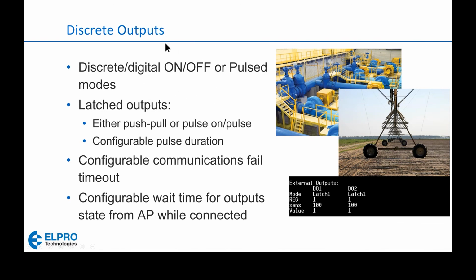So if radio communications are lost, what do we want the outputs to be doing? Do we want them to fail on? Do we want them to remain at their last known state, or do we want them to fail off? And then we have wait times so that we don't trigger these outputs immediately. We wait some period of time to see if the radio can establish communications with the access point once again.